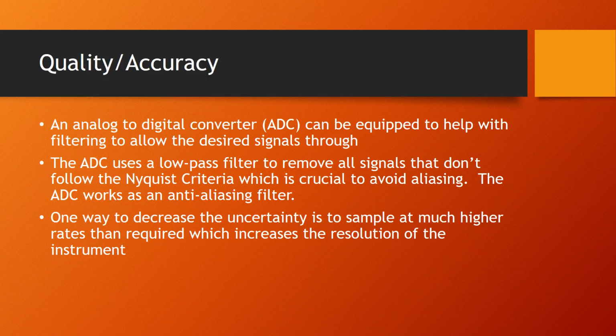With all measurement systems, quality and accuracy are very important. Seismic transducers use an analog to digital converter that can be equipped to help with filtering, allowing the desired signals through. The ADC uses a low-pass filter to remove all signals that don't follow the Nyquist criteria, which we learned about in class. This is crucial to avoid aliasing, so the ADC works as an anti-aliasing filter. One way to decrease uncertainty is to sample at a much higher rate than required, which also increases the resolution of the instrument.